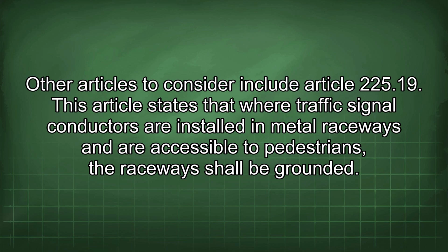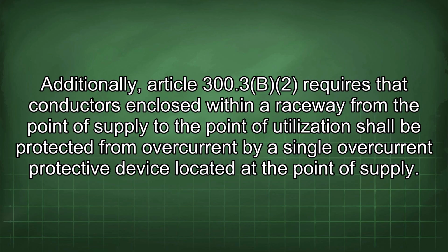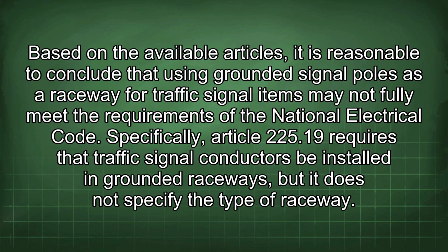225.19. This article states that where traffic signal conductors are installed in metal raceways and are accessible to pedestrians, the raceways shall be grounded. Additionally, Article 300.3b2 requires that conductors enclosed within a raceway from the point of supply to the point of utilization shall be protected from overcurrent by a single overcurrent protective device located at the point of supply. Based on the available articles, it is reasonable to conclude that using grounded signal poles as a raceway for traffic signal items may not fully meet the requirements of the National Electrical Code.